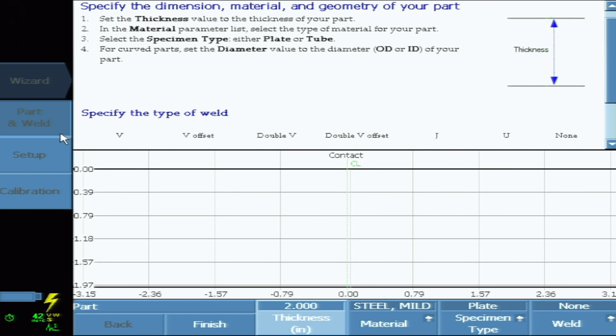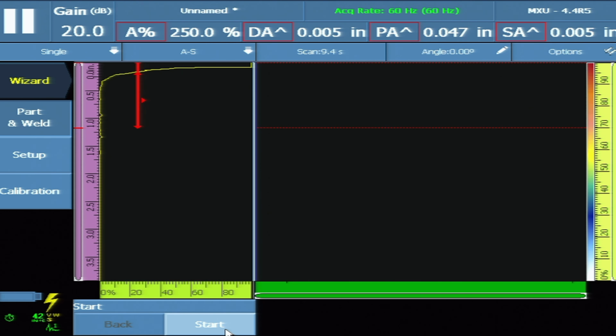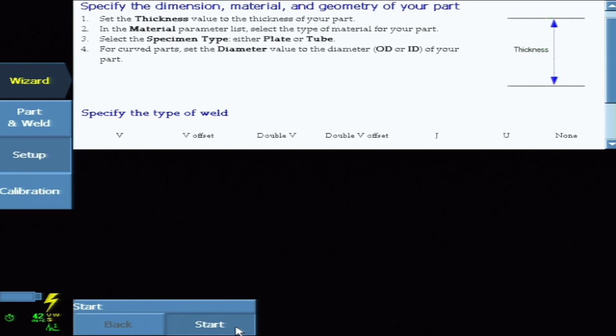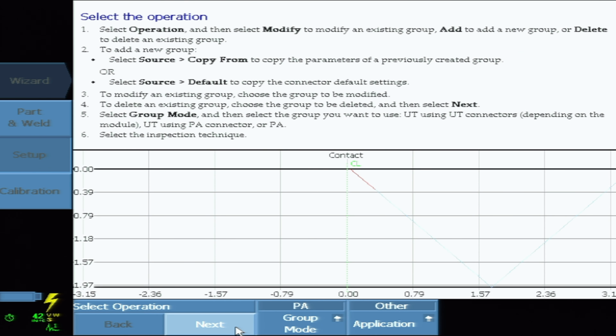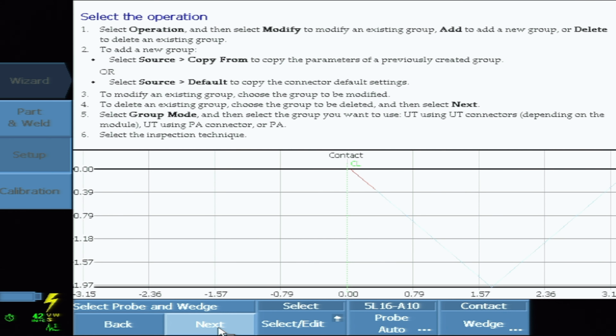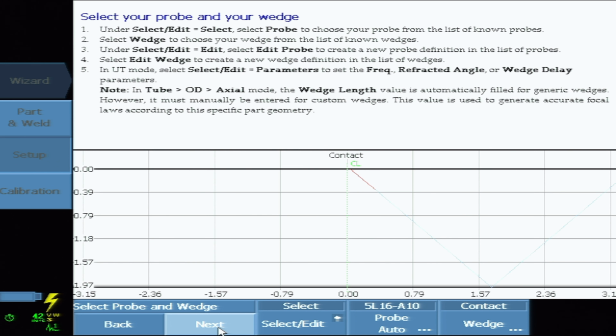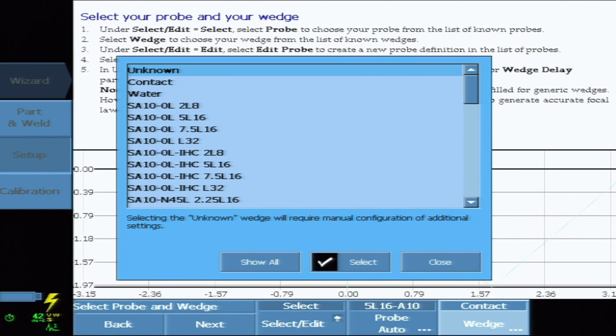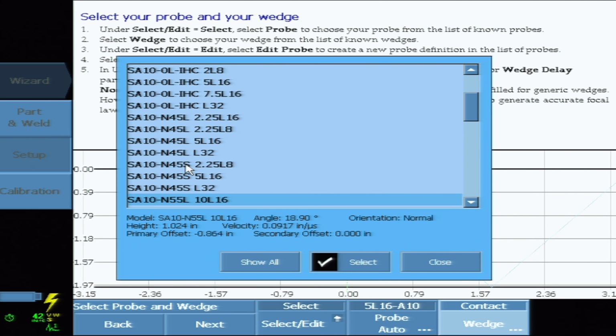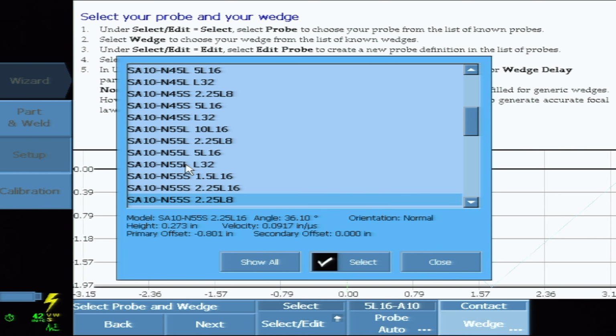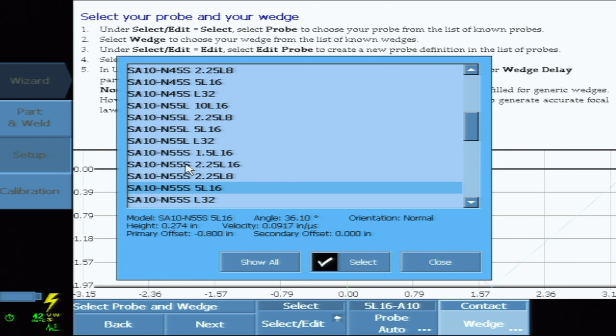So let's get to the unit. We're going to set our thickness at 2 inches. We're going to leave it on plate. We're not going to do a weld right now. We're going to go to setup. Okay, down here you're going to see phase array. You're going to see your probe, I'm sorry. Your probe's going to be right here, 5L16 A10. The machine's going to automatically read the probe. So right here where you see wedge, click on it, and we're going to look for SA10 N55S for 5L16. SA10 N55S for 5L16 right here.